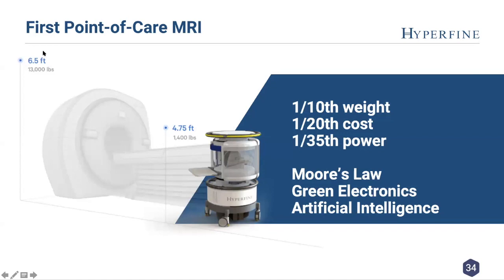As a comparison, the Hyperfine scanner versus a conventional scanner: we are much lower weight, 1400 pounds instead of 10 times that, 13,000 pounds, typical for a 1.5 Tesla scanner. We use much less power, instead of hundreds of amps we use less than 15 amps. Our peak power consumption is around 900 watts during some of our sequences.